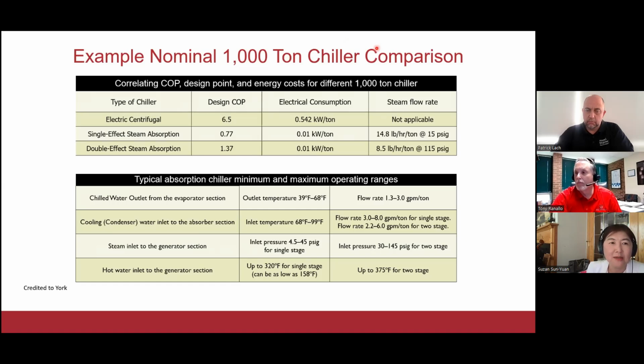credited to York. The data on the top table shows that although the absorption chillers have low COP, you could tell the electric consumption is extremely low. The bottom table lists the operation and output range for both types of absorption chillers. Both of them utilize lithium bromide solution. Next slide, please.